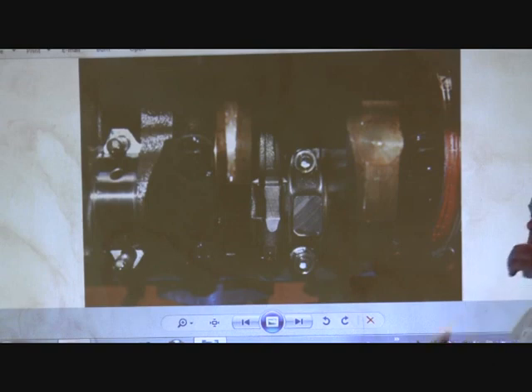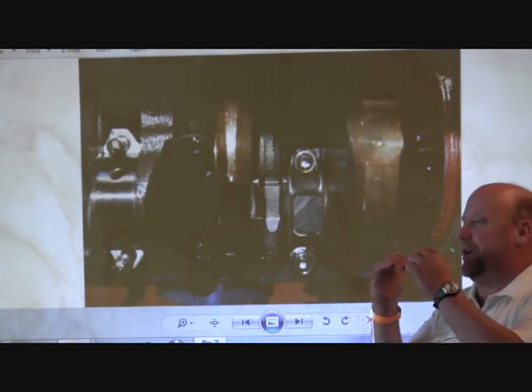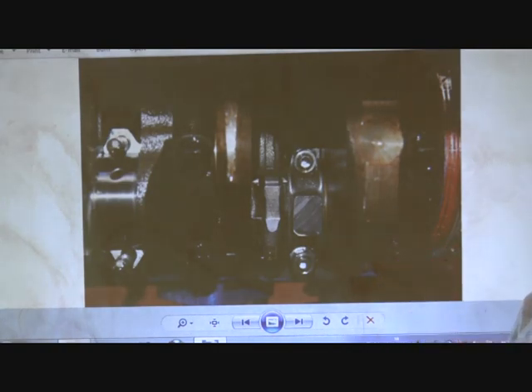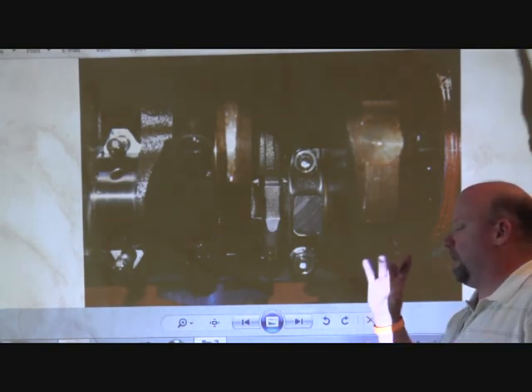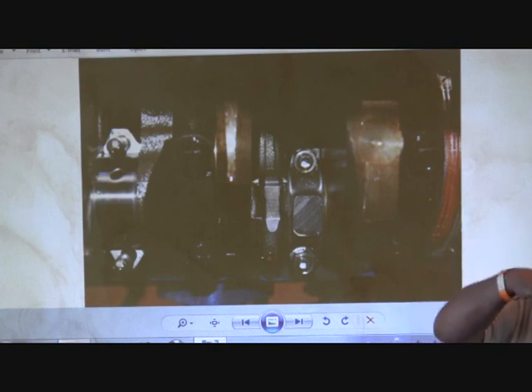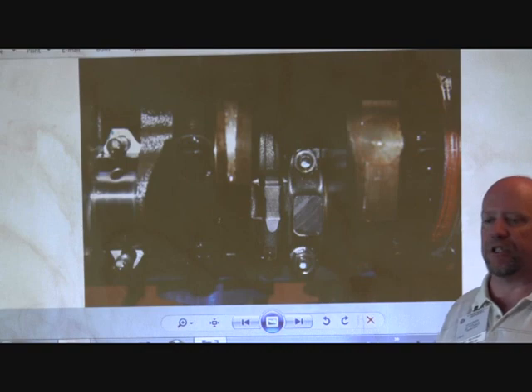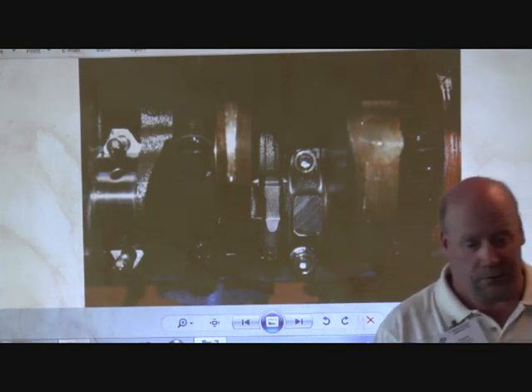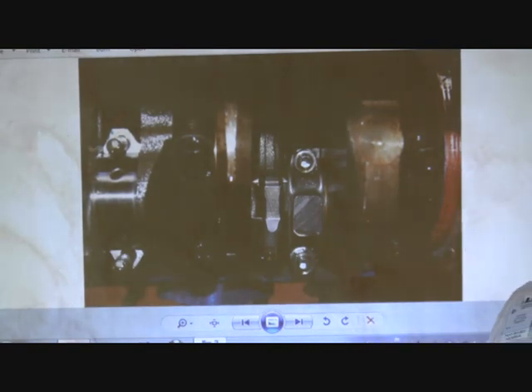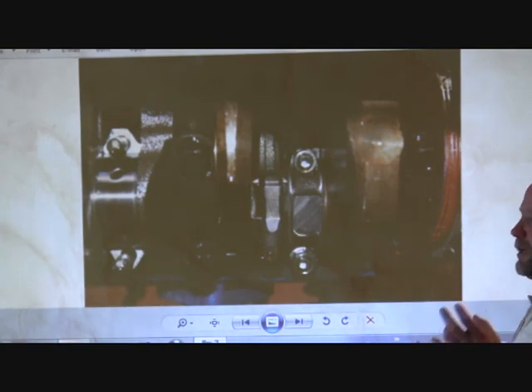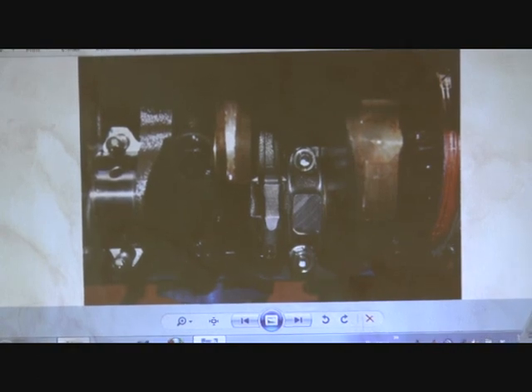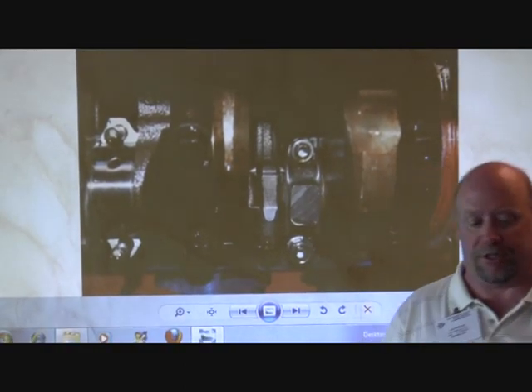Bearing material has different layers of metal at different thicknesses. If you do an oil analysis, which just requires taking a clean bottle, putting some oil in it, and sending it to a company, they'll send back a 3-page report listing every chemical found in that oil. They'll tell you if it has antifreeze residue, or if it has babbitt, clevite, or copper, the three materials generally used in bearings. If you get down to the copper, the bearings are done, you're pretty much out of bearing material.